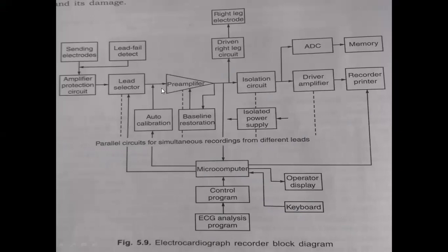Here, the lead selector is a switch. With this lead selector switch, we can select all the 12 electrode combinations, with which the ECG signals obtained from the patient are selected.